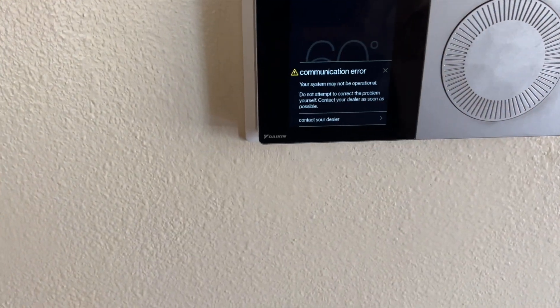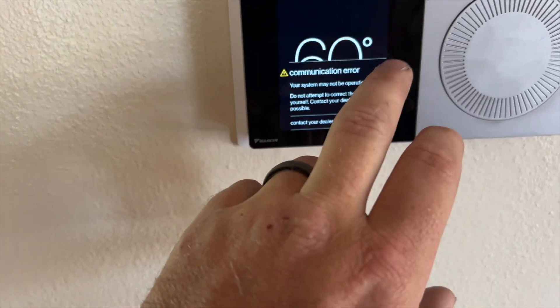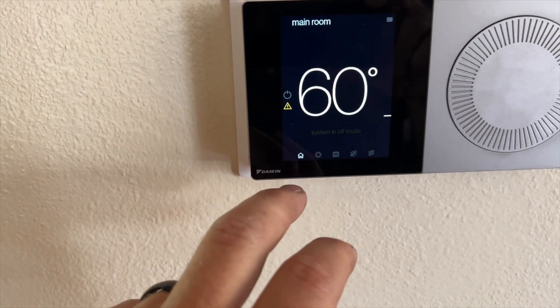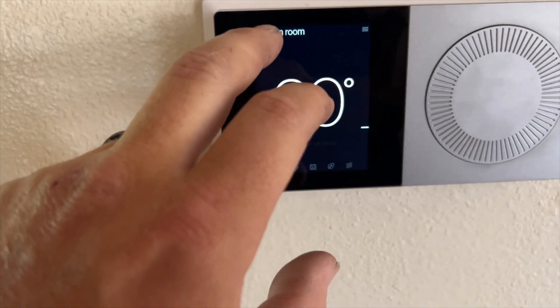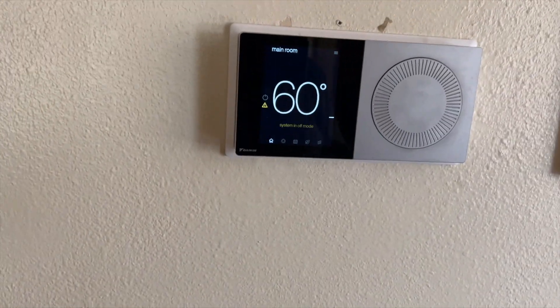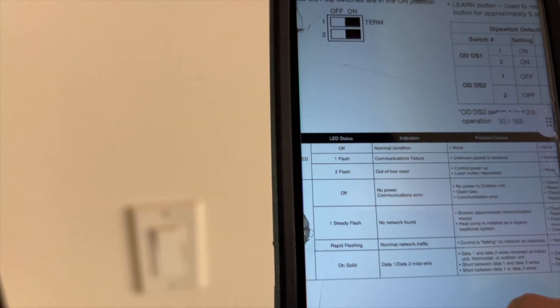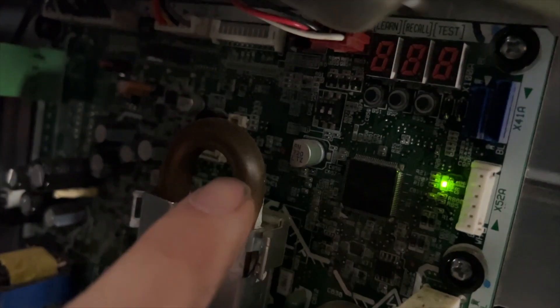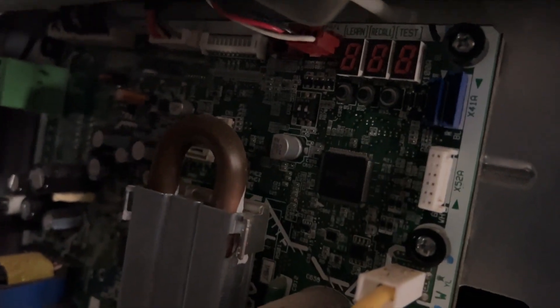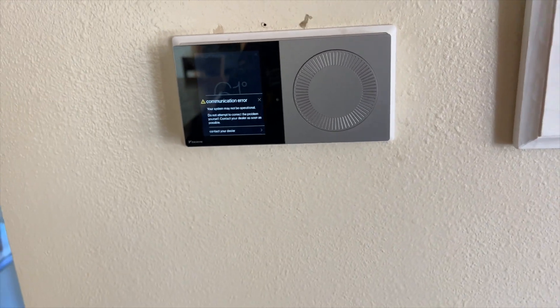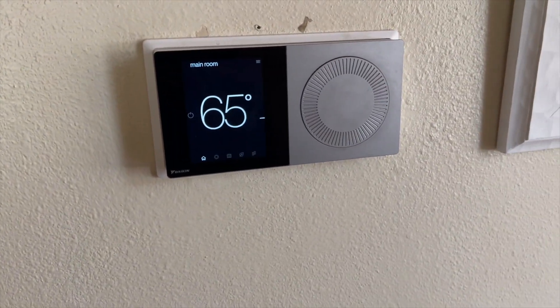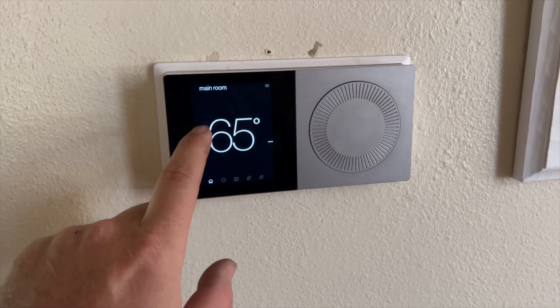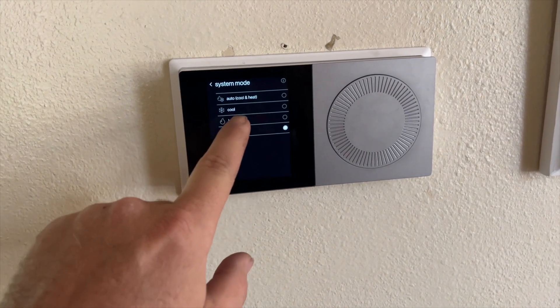Now we have a communication error on the display. According to the manual, a red communication error means an unknown packet is received — depress the learn button. The learn button is the one all the way to the left. I pushed it and held it, and now we have everything back. Let's try to get it to heat and see if it stays working.